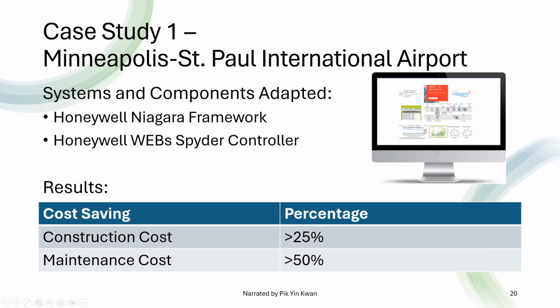In this project, Honeywell Niagara Framework and Honeywell WEBs Spyder Controller are adopted. They provide an open operating system that can connect and control the systems from a web browser. With the assistance of the Spyder Controller, the airport could also keep the existing sensors, valves, dampers, and wiring. This resulted in reducing more than 25% of construction costs and 50% of maintenance costs.